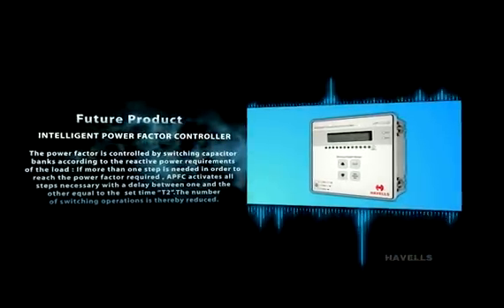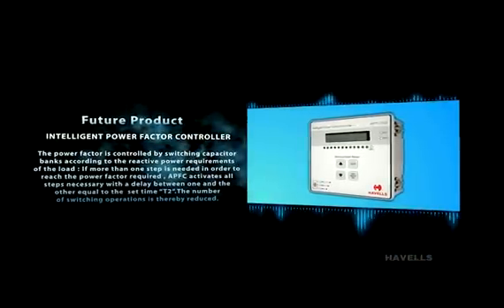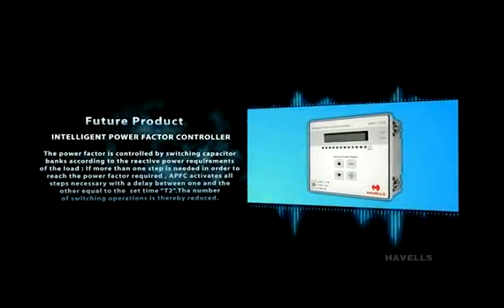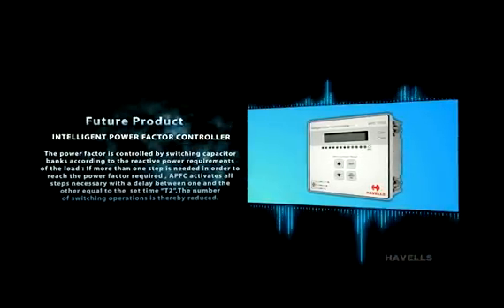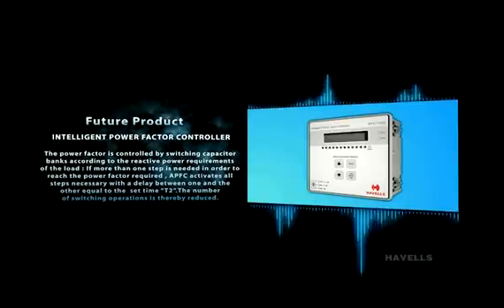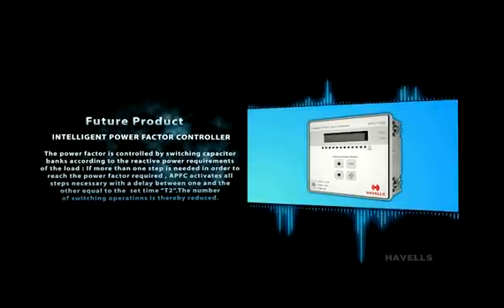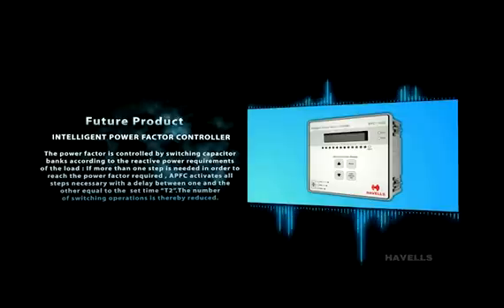Future product: Intelligent power factor controller. The power factor is controlled by switching capacitor banks according to the reactive power requirements of the load. If more than one step is needed in order to reach the power factor desired, APFC activates all steps necessary with the delay between one and the other equal to the set time T2. The number of switching operations is thereby reduced.